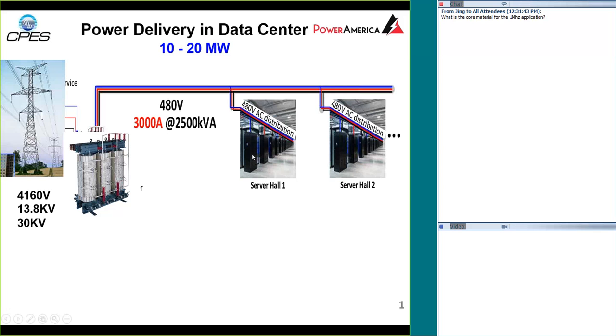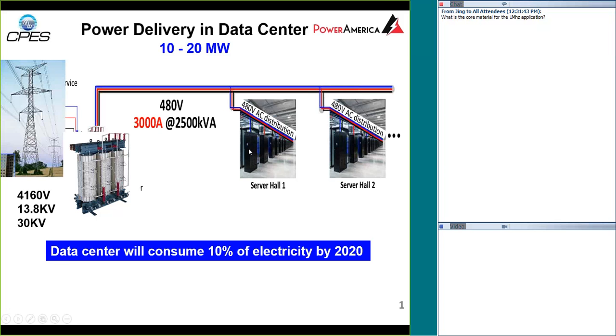There is a loss in the cable. In the data hall you have 480 volt three-phase AC and want to distribute it to the cabinet level. The server cabinet can only take single phase. Now keep in mind: data centers will consume 10% of electricity by 2020. One percent improvement in efficiency means 16 terawatt hours — 16 × 10¹² watt hours. Every bit of power dissipated in the air requires air conditioning to cool it, so multiply that by a factor of two.